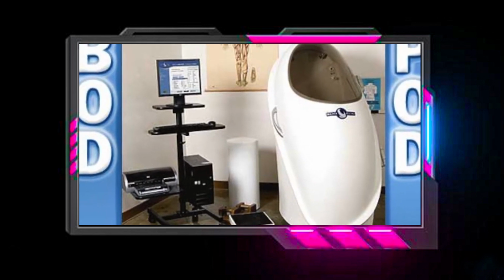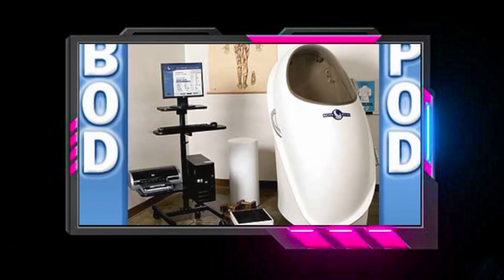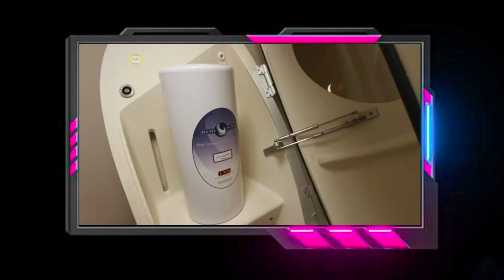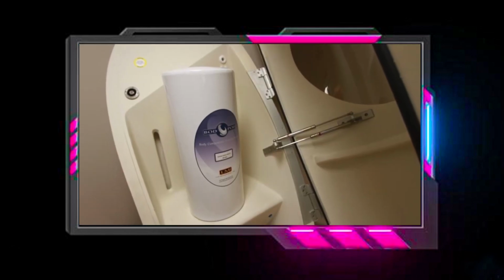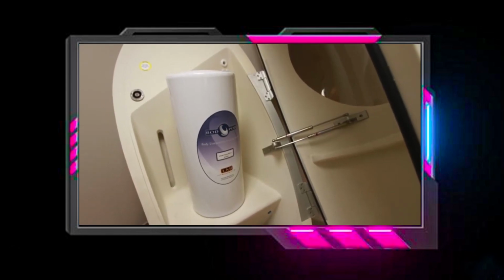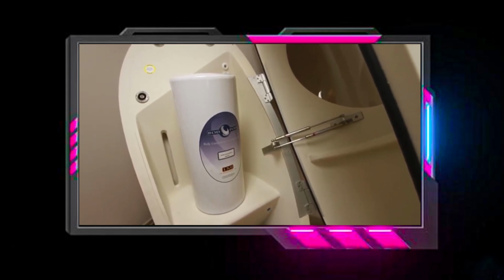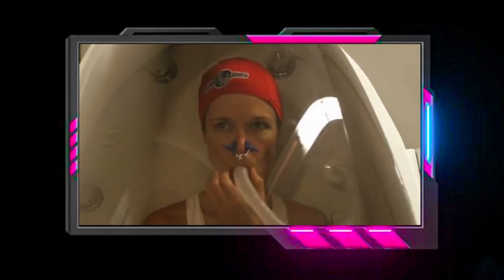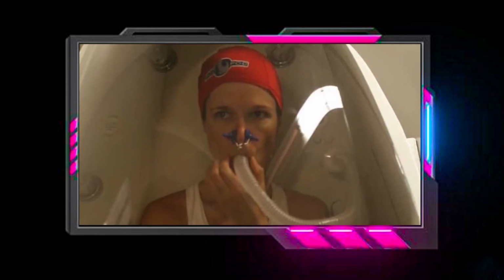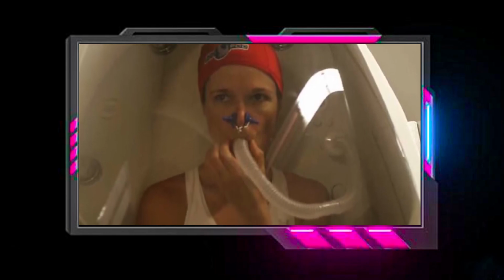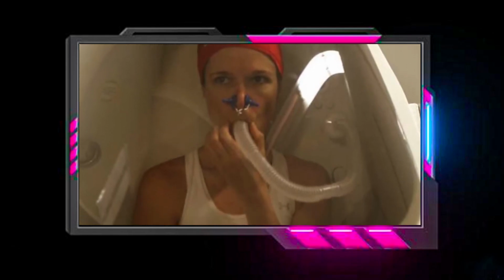This is called BODPOD. A BODPOD uses a mechanical diaphragm to create small volume changes in a confined and controlled space, then measures pressure responses. A person's weight, age, gender and height are recorded before the test and the chamber is calibrated.